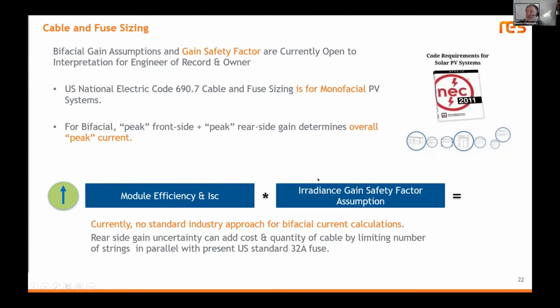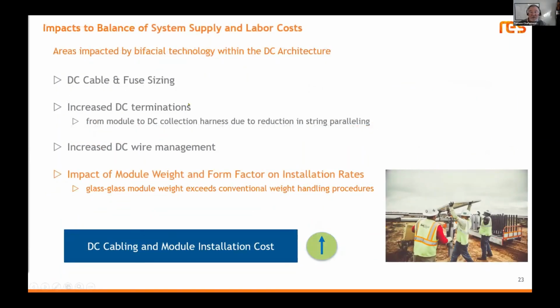And so your increased module efficiency times irradiance gain, safety factor assumption, etc. Well, because there's no standard industry approach for bifacial current calculations, you have to calculate in that uncertainty, and that can add cost and quantity of cable, limiting the number of strings you can put in parallel. Because in North America, you use a 32 amp fuse. So all these considerations need to be made, and again you have an area where you may add cost. And then among these various considerations, fuse sizing, DC terminations, you may have more DC terminations to do, increased DC wire management. Well, don't underestimate the impact of module weight and form factor on installation rates. Glass-glass modules are heavier, typically 30% heavier compared to a monofacial module with a glass backsheet.